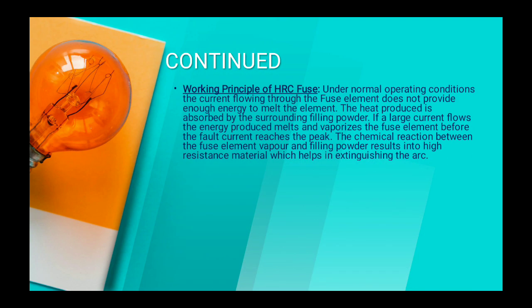Now the working principle of HRC fuse. Under normal operating conditions, the current flowing through the fuse element does not provide enough energy to melt the element. The heat produced is absorbed by the surrounding filling powder. If a large current flows, the energy produced melts and vaporizes the fuse element. Before the fault current reaches the peak, the chemical reaction between the fuse element vapors and filling powder results in high resistance material which helps in extinguishing the arc.